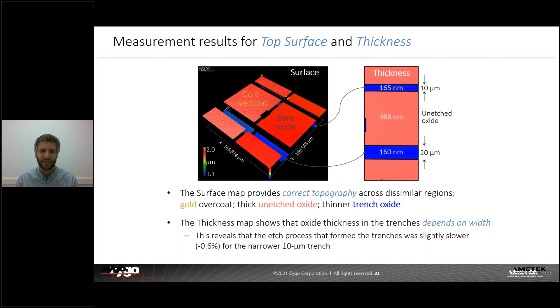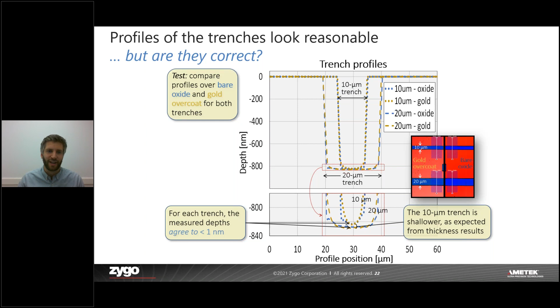And we see, using the gold overcoated region, a good way to test if our film is properly measuring thickness. So by comparing the depth of the trench in the gold coated region with the bare region, we see a nice agreement to better than 1 nanometer of the depth of those trenches and the profiles across them. So that gives us some nice confidence in the technique.